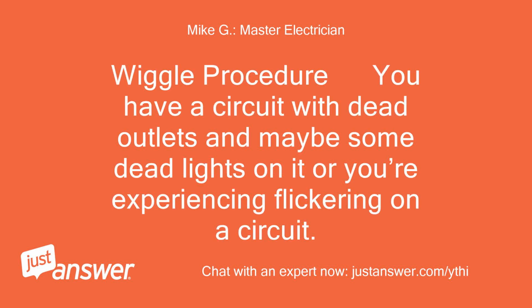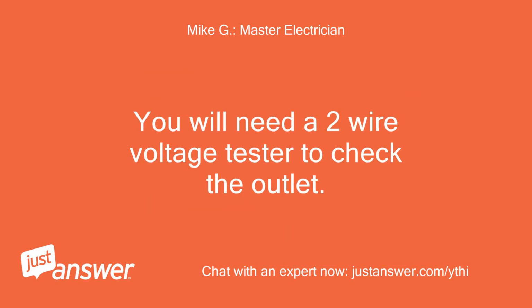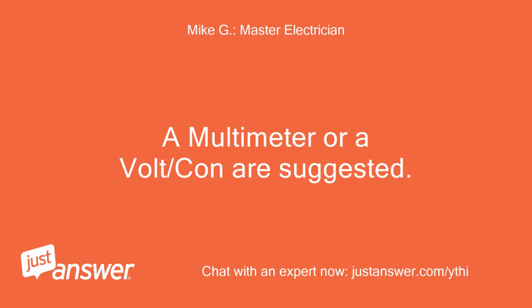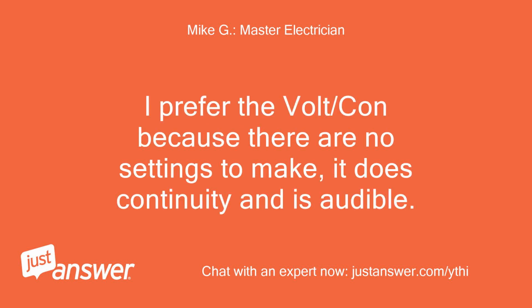Wiggle procedure: you have a circuit with dead outlets and maybe some dead lights on it, or you're experiencing flickering on a circuit. You will need a 2-wire voltage tester to check the outlet. A multimeter or a volt/con are suggested. I prefer the volt/con because there are no settings to make, it does continuity and is audible.